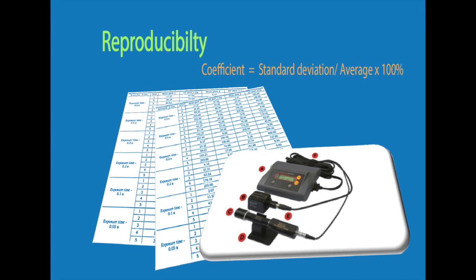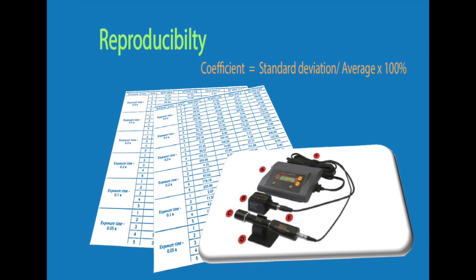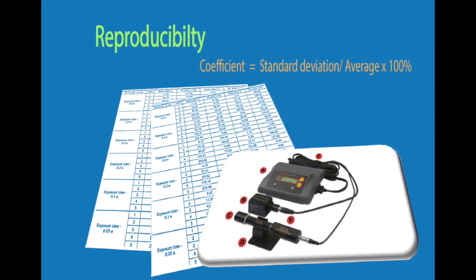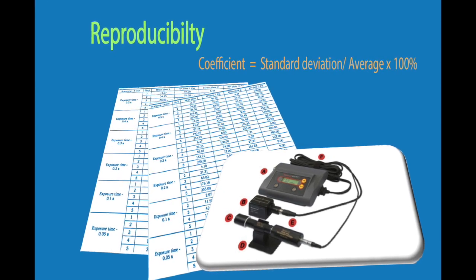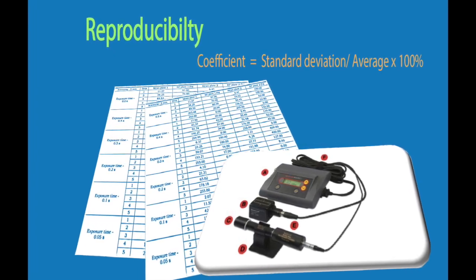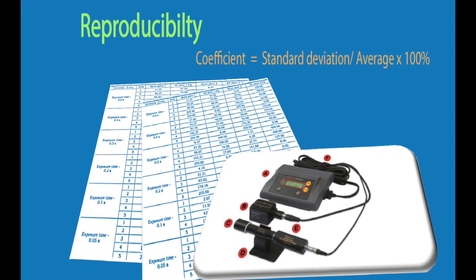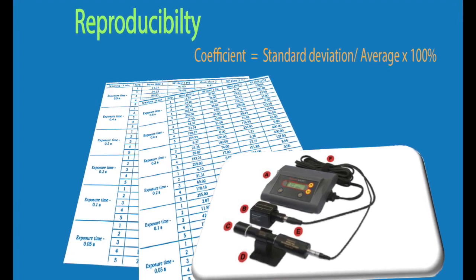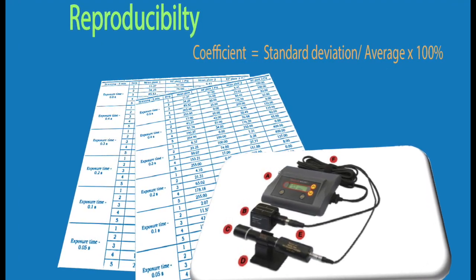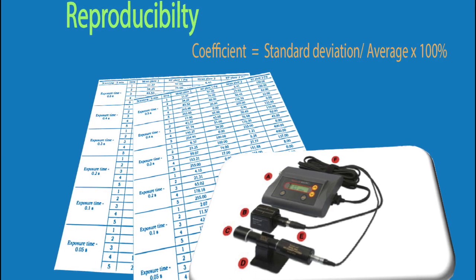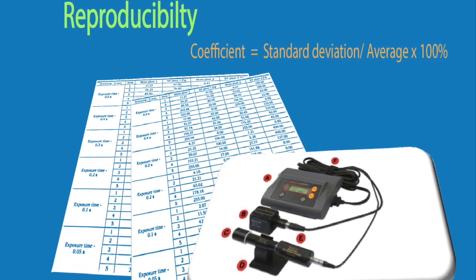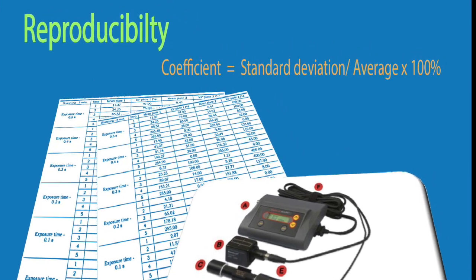When performing quality control testing of technical output of radiologic equipment, it is important to assess the accuracy of the data collected and that the equipment maintains consistency in that output from one exposure to another when using the same technical factors, and for this reason we need to know the amount of variation we get. To ensure this, we can calculate the coefficient of variation as follows.